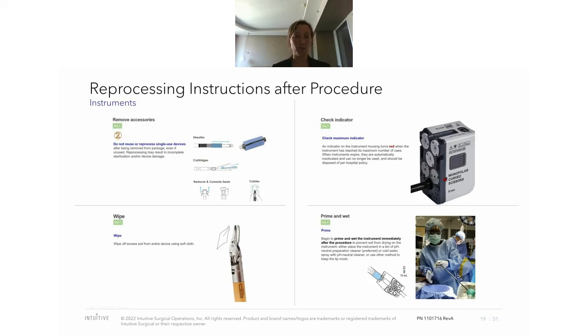The other part of keeping prime and wet is to keep the tip moist. And I was very happy when Bart mentioned that he's using in his facility the Distel Wet Set. That is one of the options to keep the tips of the instrument moist. There's also an option to use a towel, or you can use a spray. Whatever method you're using, it is very important to follow the prime and wet step. Depending on the jurisdiction or the region you're working in, there might then be a chemical pre-disinfection, or if that is not required, that is also an optional step, and then the transport to the CSSD.